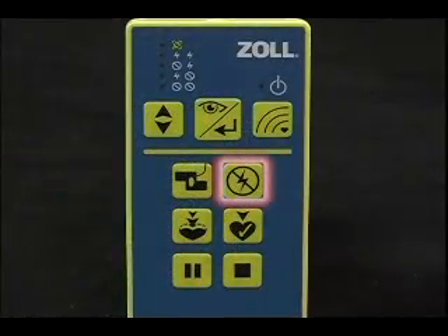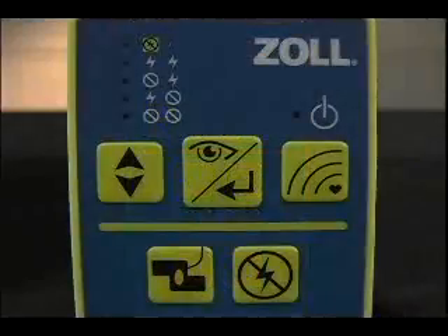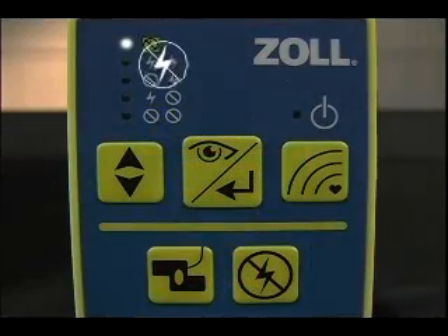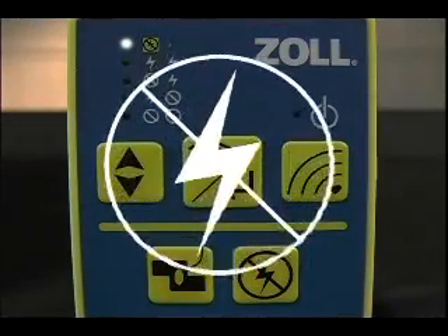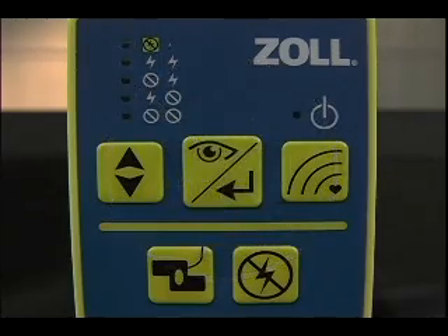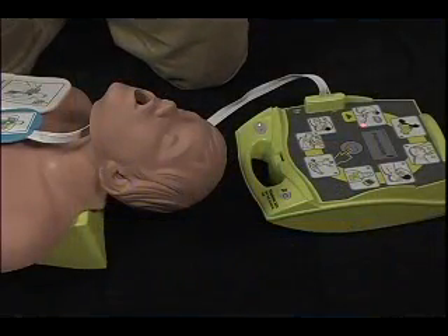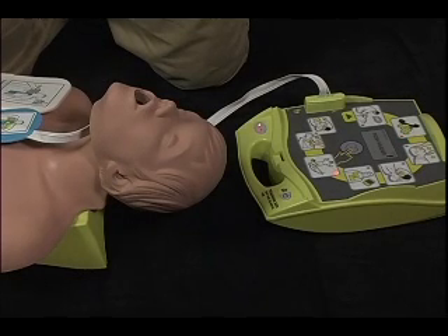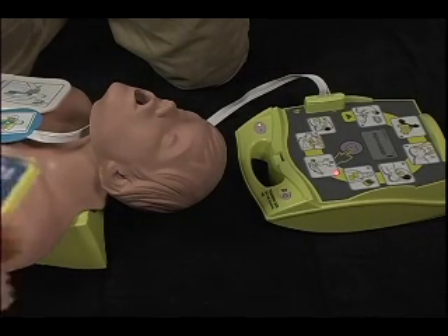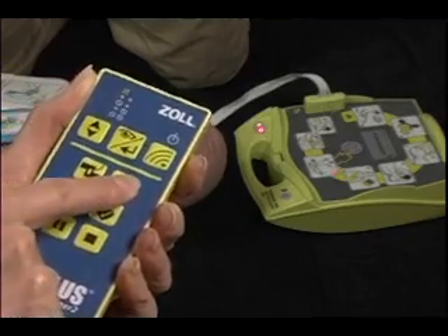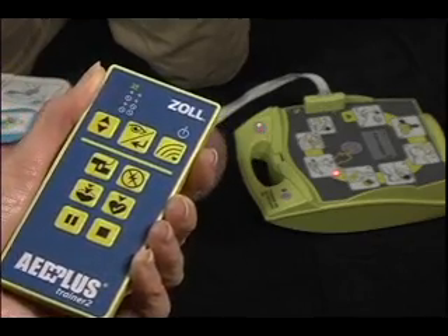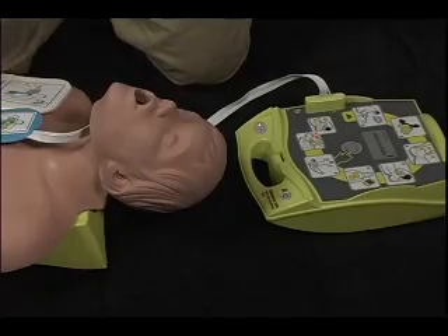The No Shock button on the top right is used to call for a result of no shock advised on the next heart analysis. It can only be used during a manual scenario and not during one of the 4 fixed scenarios. By default, in every manual scenario, the heart analysis will always advise a shock. Push the No Shock button once to force the next heart analysis to advise no shock.